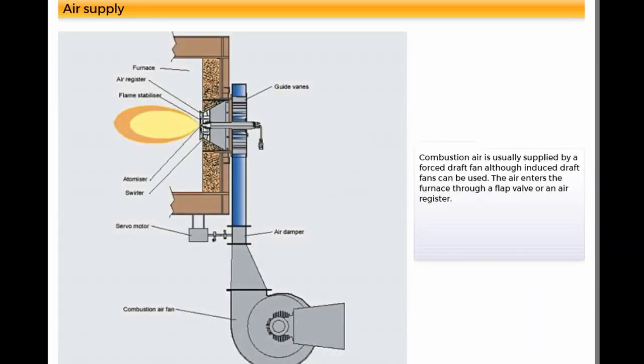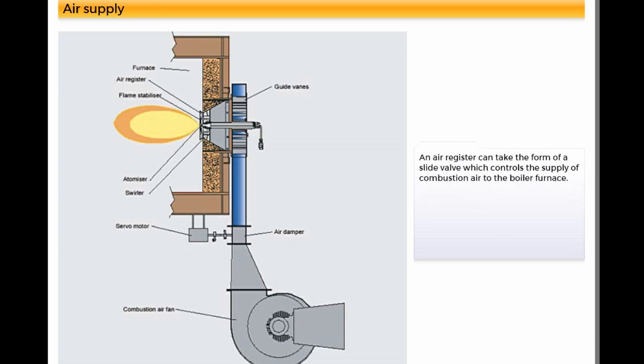Combustion air is usually supplied by a forced draft fan, although induced draft fans can be used. The air enters the furnace through a flap valve or an air register. An air register can take the form of a slide valve which controls the supply of combustion air to the boiler furnace.